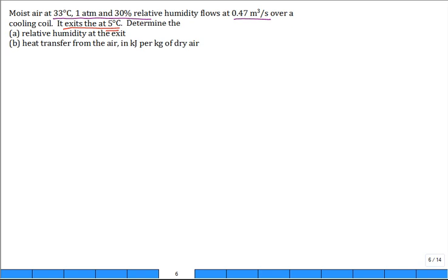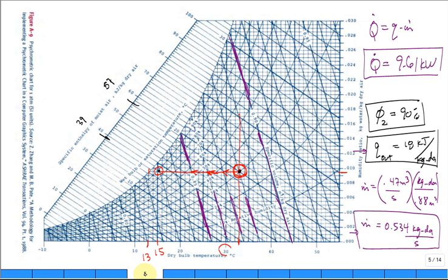It's below the dew point temperature, so it's going to cool until it hits 13. And as you try to go from 13 to 12, it'll have to reduce the amount of humidity because it'll hit 100% relative humidity. Some will dew out. And then you'll continue to cool down to 10, then continue until you get down here to 5 degrees C, and that's where it'll stop right there. So your ending point has shifted to this point down here. So this is the new point 2, the exit. So the relative humidity at this point right here, phi, is 100%.